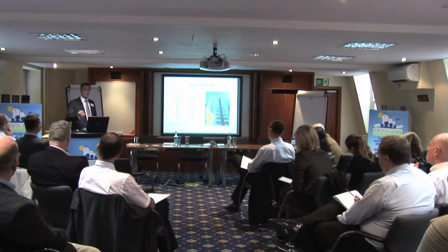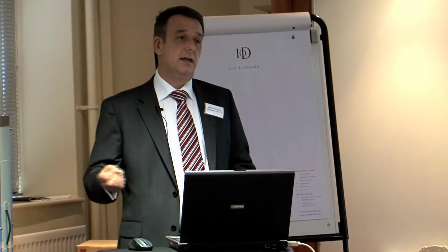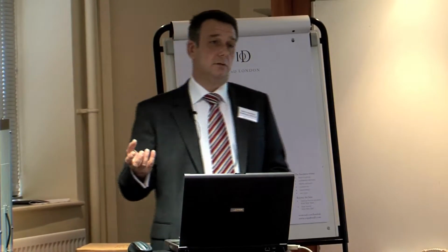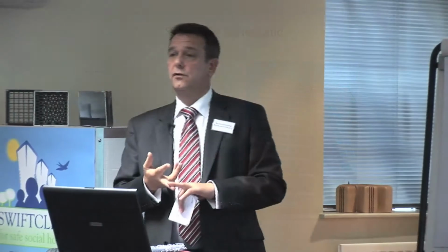If you can imagine what's up in these ductworks, if it's the kitchen extractor they've got, it's normally going to be grease, moisture, a bit of dust. The bathroom, it's paper, lint, bits of skin, all combustible. So if a fire was to start in a flat or one of these social housing and it went up through this little shunt duct, it could ignite straight away. It's got all the elements there for a fire. You've got the ignition, you've got the fuel, and you've got the oxygen. So it's important to have these cleaned on a regular basis.